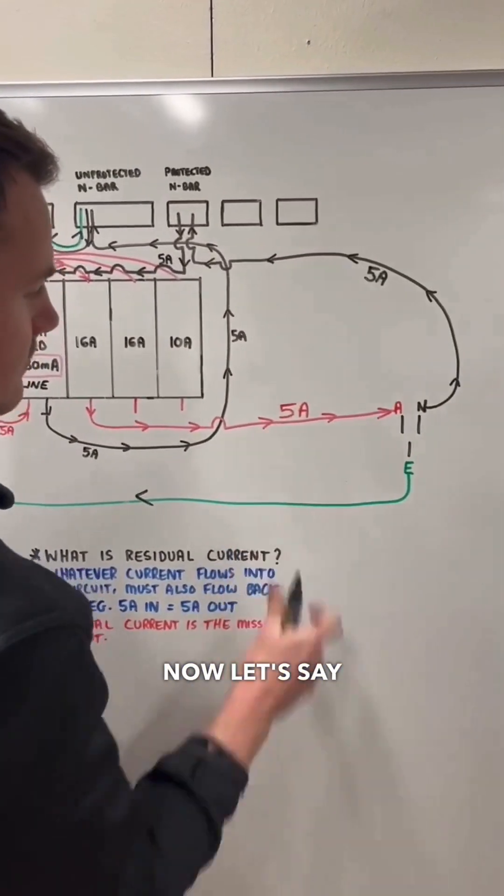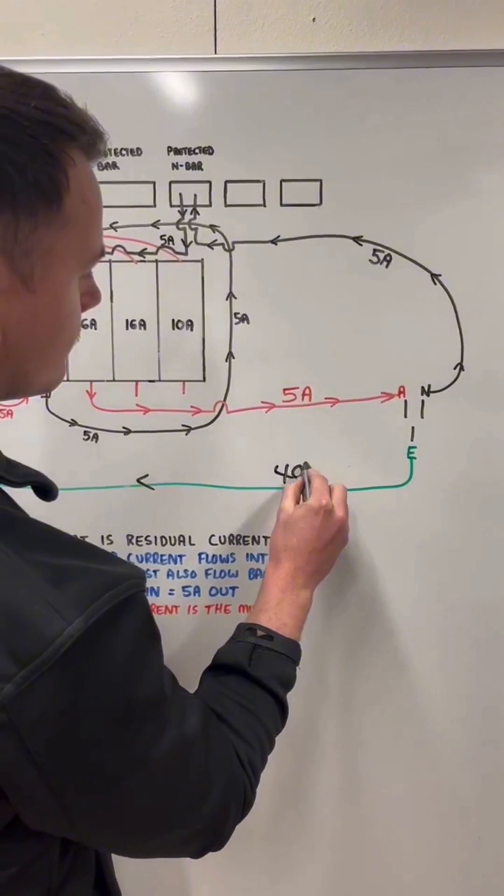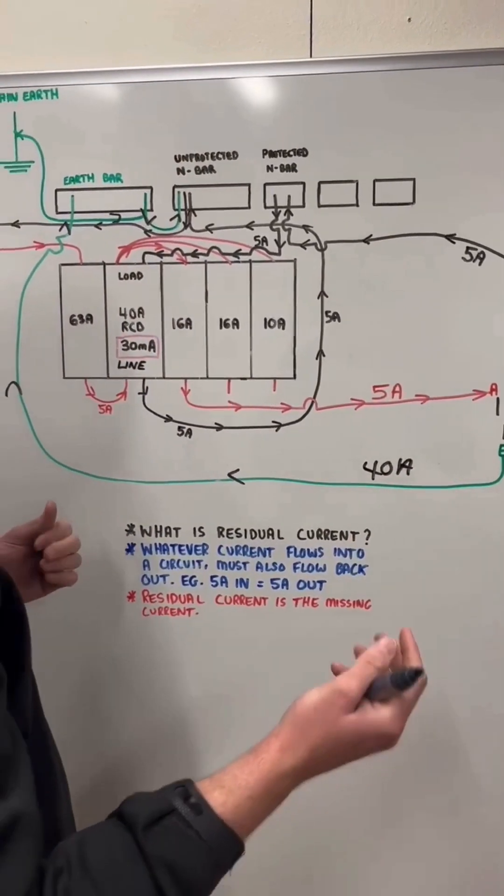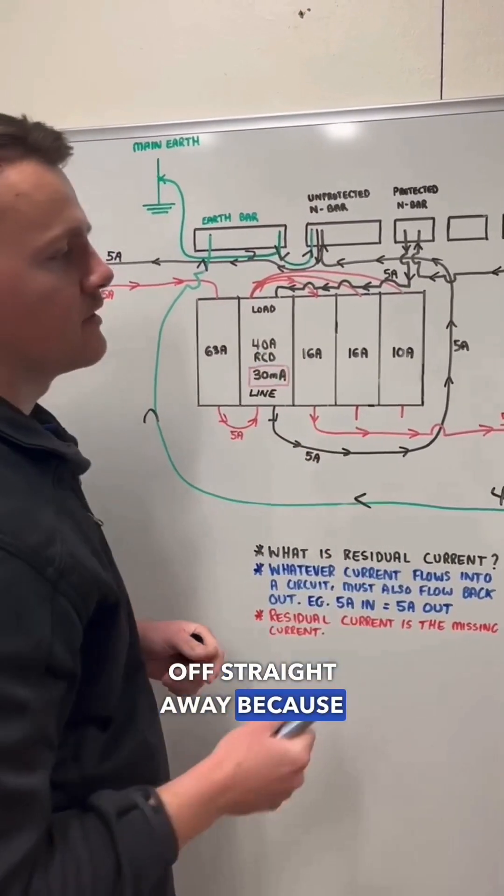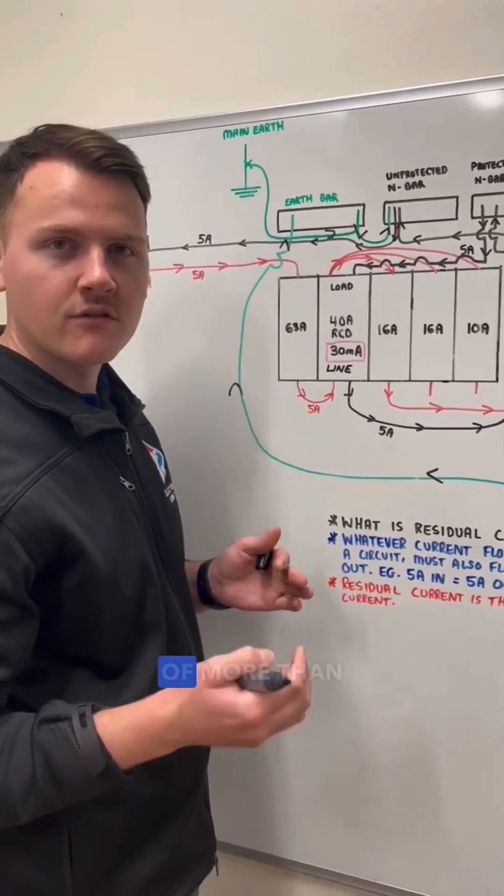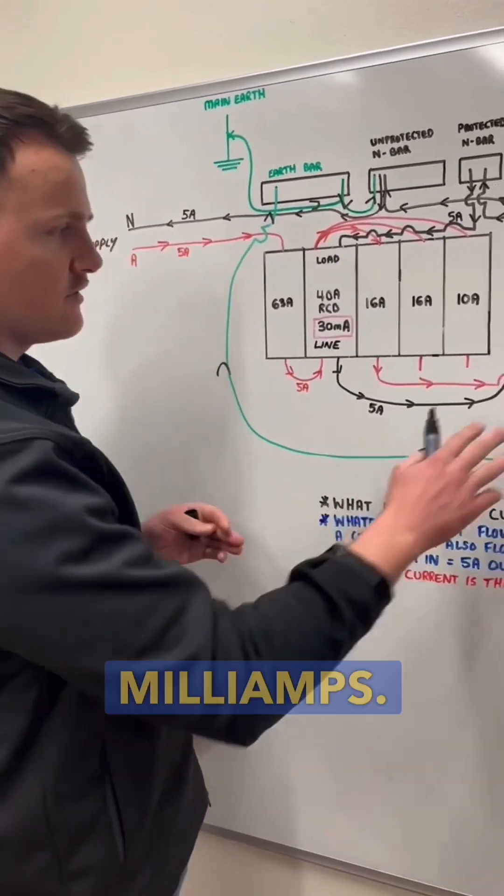Now let's say we have 40 milliamps returning through earth. So we've got a bit of earth leakage. This will trip off straight away because it's detected an imbalancing current of more than 30 milliamps. So this is residual current.